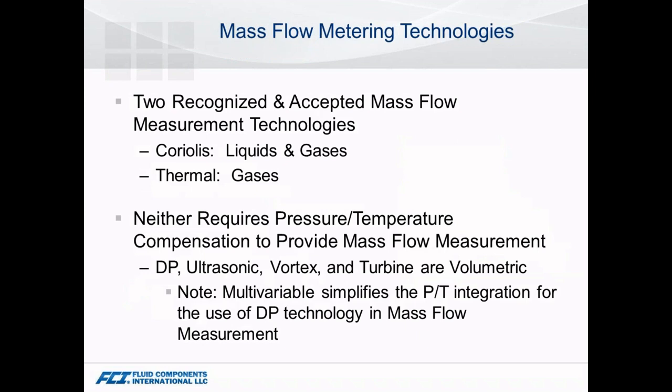Now let's change over to the metering side — specifically mass flow metering. Within the industry, there are two recognized and accepted technologies, with thermal being one of them. Coriolis works for many media, while thermal is really focused on gases. They are both mass flow because neither one requires a secondary pressure-temperature compensation to convert a volumetric reading to mass flow.